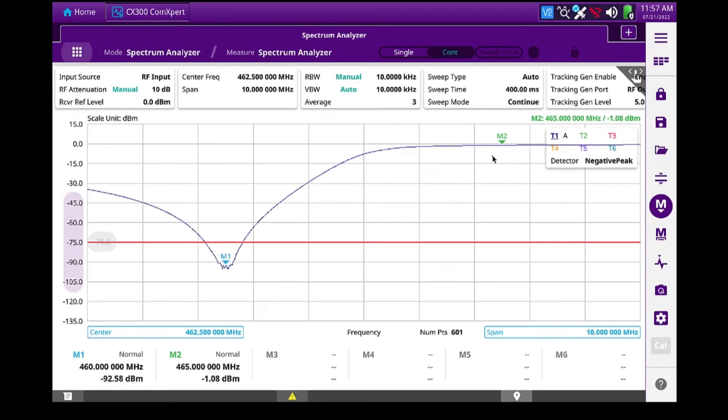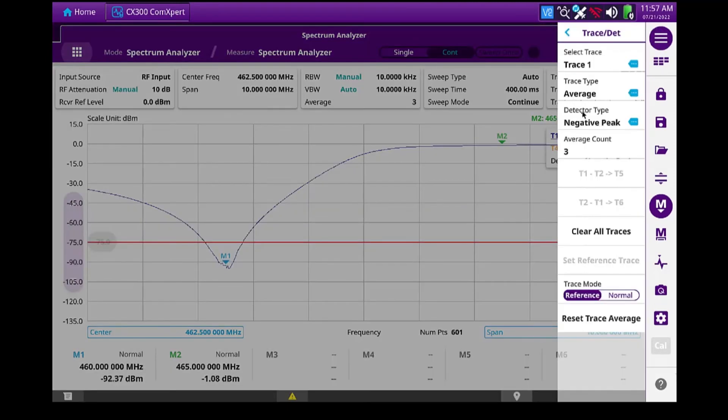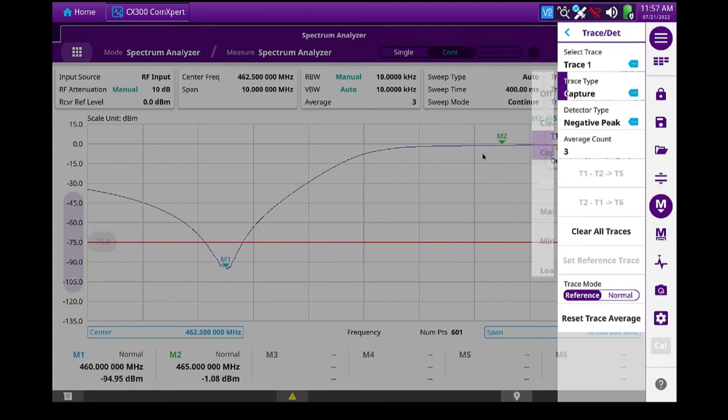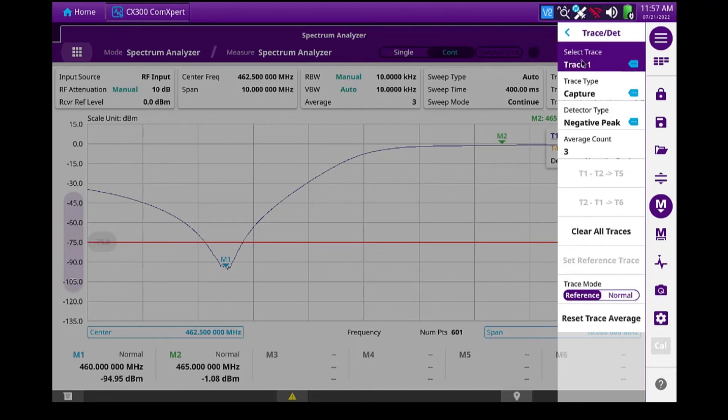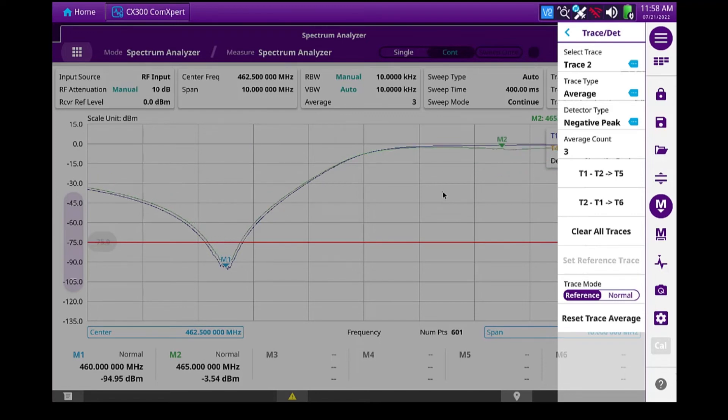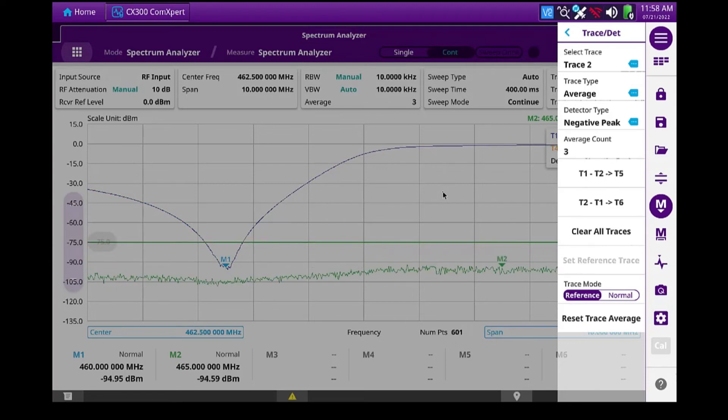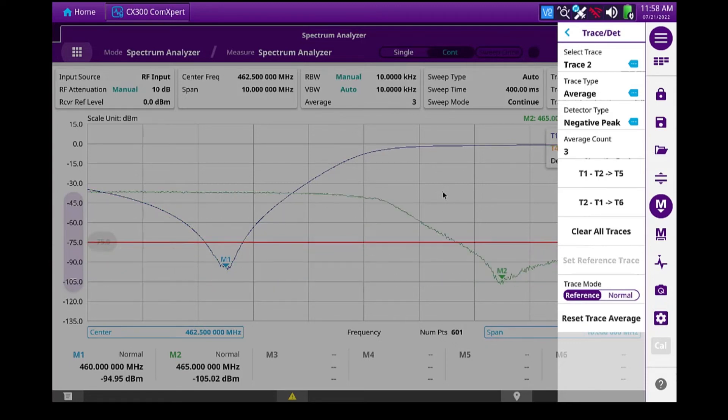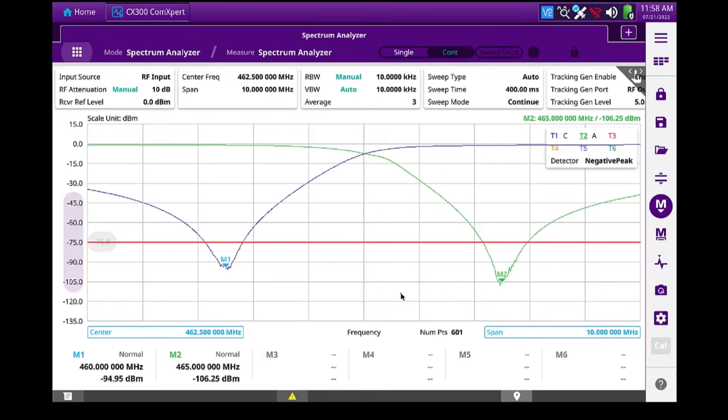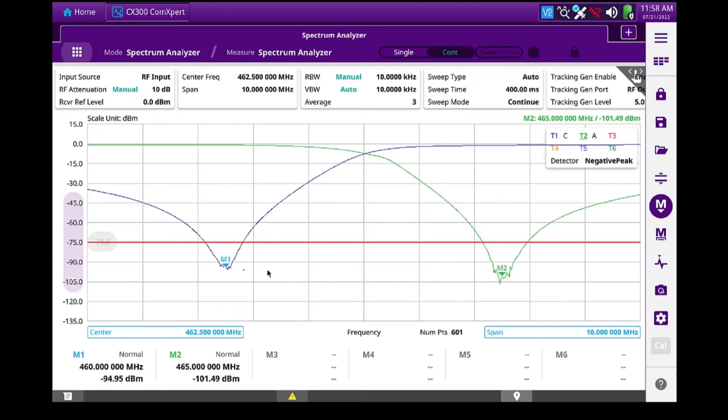And other things I can do is I can come up, I can set this trace type to capture. Now that one's locked in. And I can select a second trace. I'll set it to average. And I'll move my cable and load again. So now I've got a view of both sides. And the marker is measuring the live trace on marker two, while marker one is measuring the captured trace.